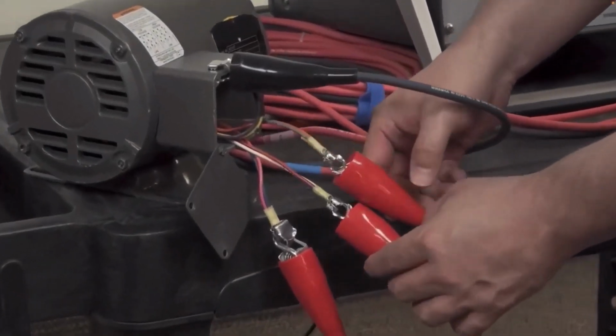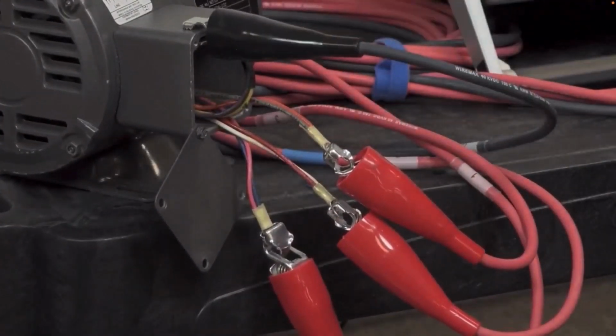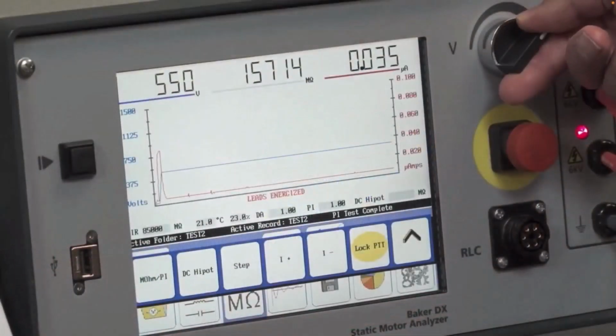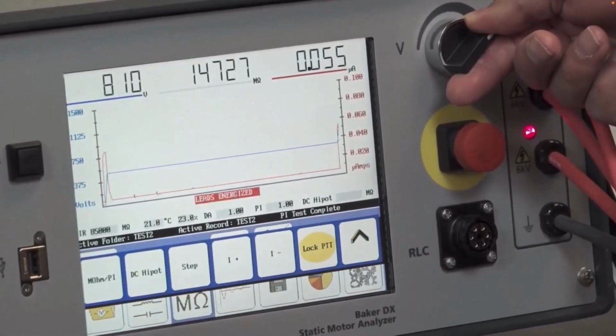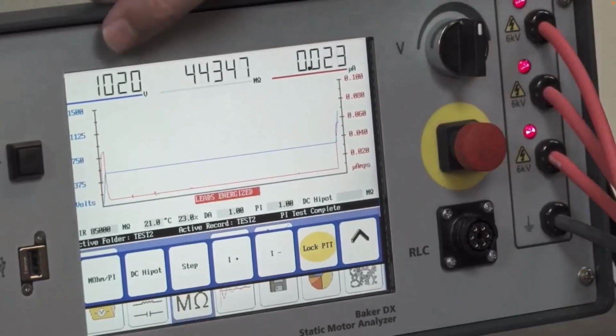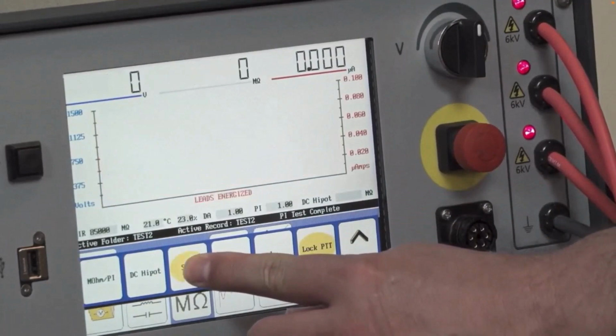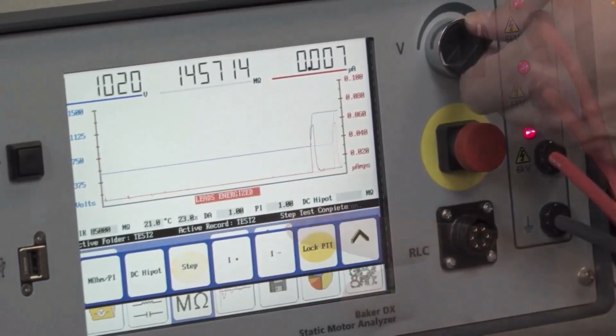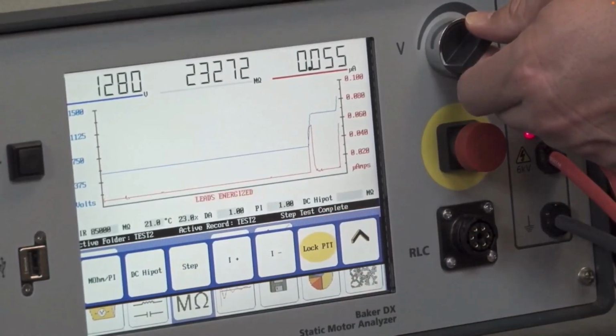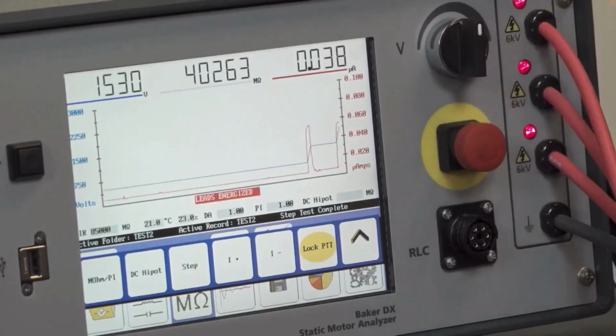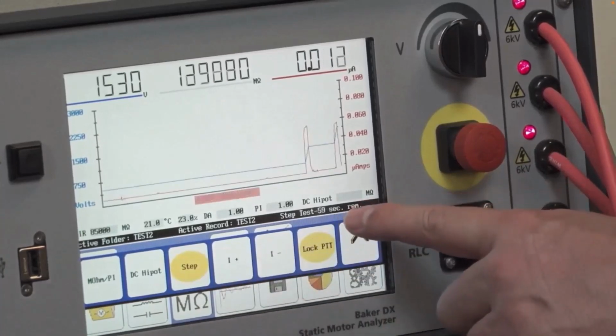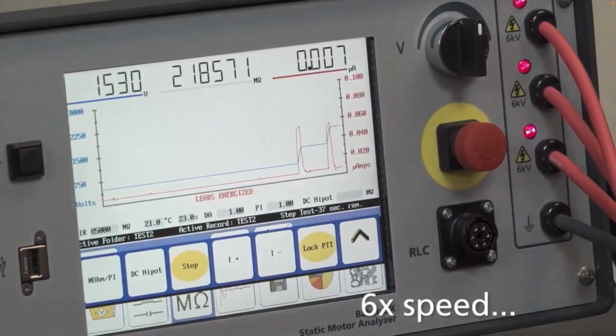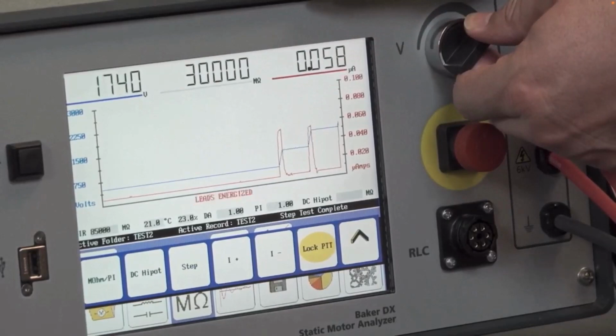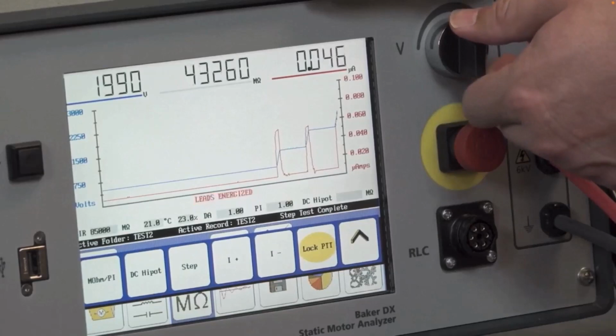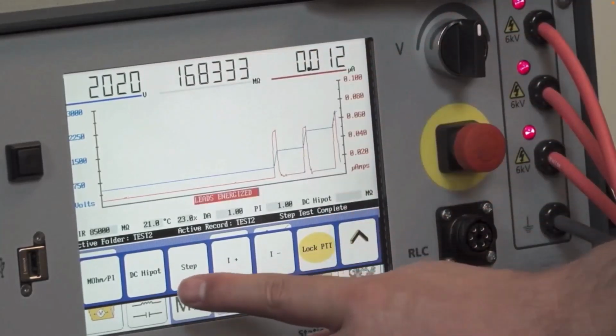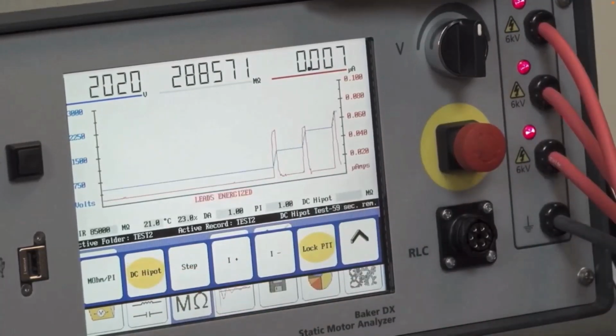All right, so let's review how a DC high voltage potential test works. DC voltage is applied to open, disconnected windings by the high pot tester or motor analyzer. The DC voltage potential in the windings is rapidly raised to a predetermined level, or raised in steps up to this level, depending upon what test method is going to be used. As the voltage is raised, several currents, as discussed earlier, will flow into and possibly out of the windings to ground. The combined total of these currents are measured by the high-pot tester. And here we see a demonstration of the step version of the high-pot test. At the last voltage level, we then look at the high potential reading.